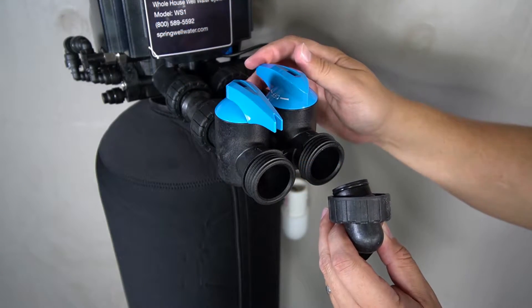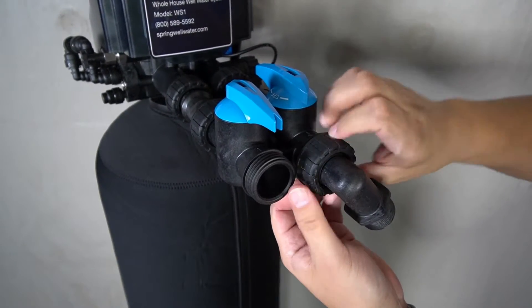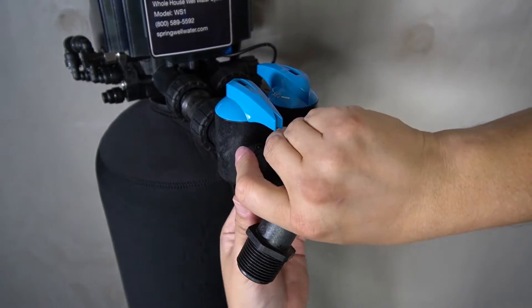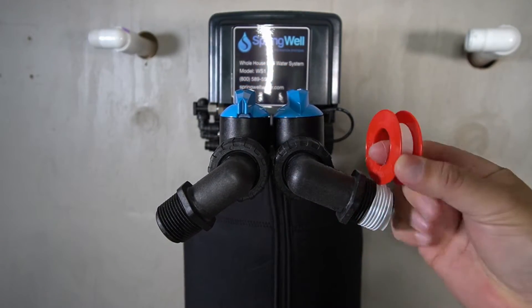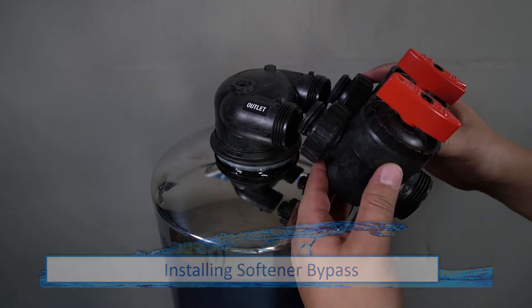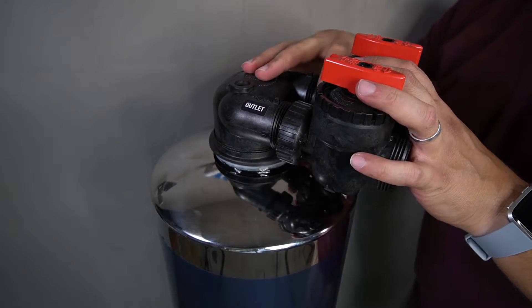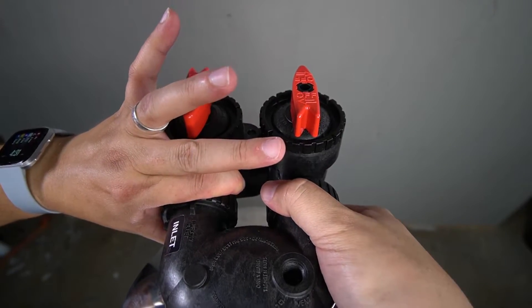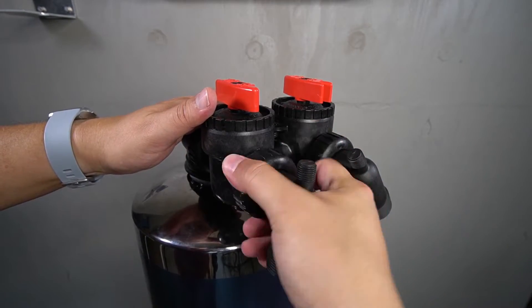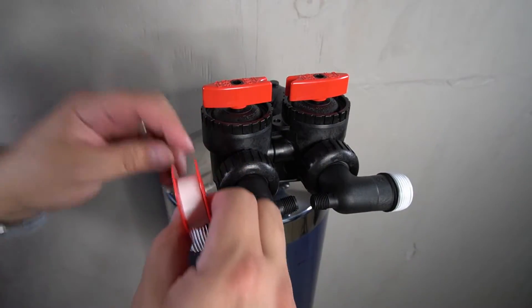The MNPT fittings will now be connected to the other side of the bypass. They have a rubberized connector that will insert into the opening and a fastener that will also need to be fully tightened. Repeat this with both of the MNPT fittings. Apply plumber's tape to the threads on the other end of the fittings. The salt-free softening tank will also need to be prepped — the bypass valve with the red levers will need to be attached to it. Insert the rubberized fittings into the connections and fully tighten the connectors. A pair of MNPT fittings will also be attached to the bypass on the salt-free softening tank, and plumber's tape will need to be applied to the threads on the other end of these fittings.